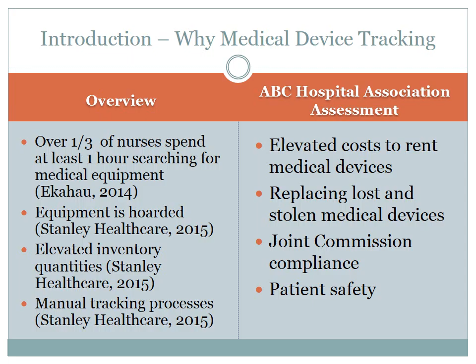Finally, an RTLS tracking system will provide ABC Hospital Association with improvements to patient safety by ensuring that staff can accurately track a device involved in a critical patient event from that patient's room through the entire sterilization process, and finally down to the clinical engineering department to be checked for issues. This will help ensure that a medical device isn't incorrectly placed back in patient use after the sterilization process.